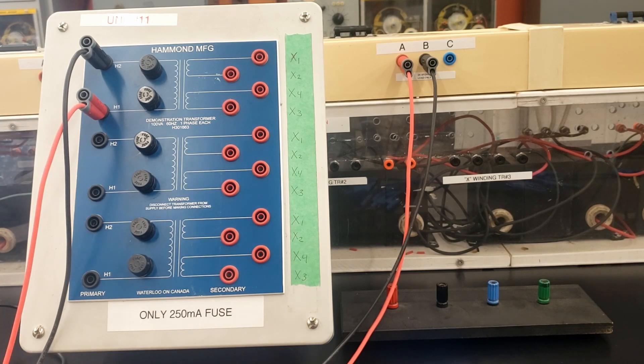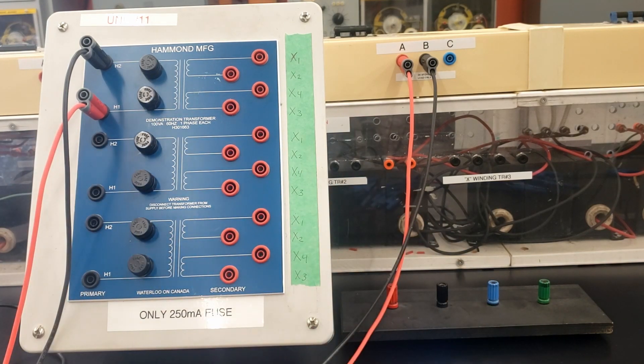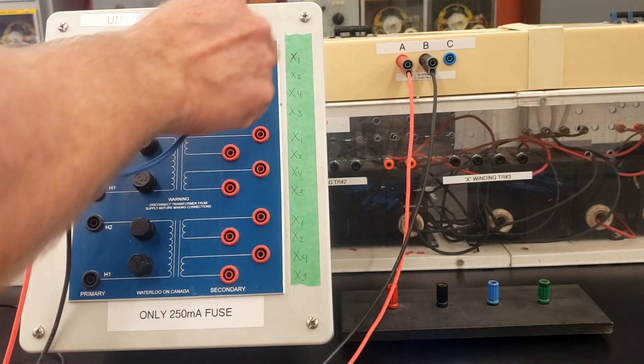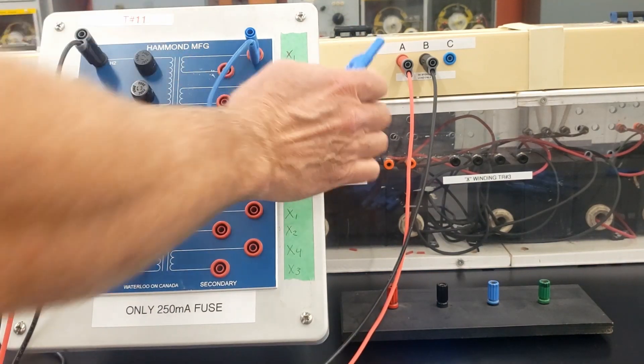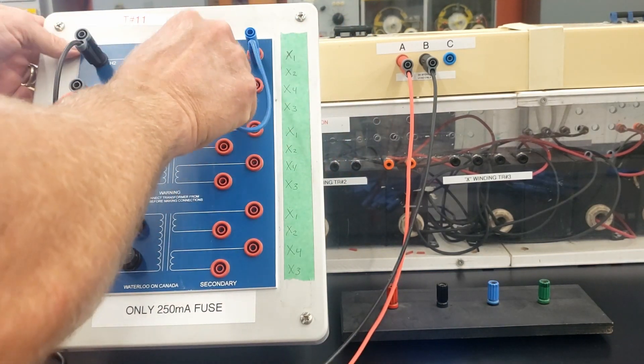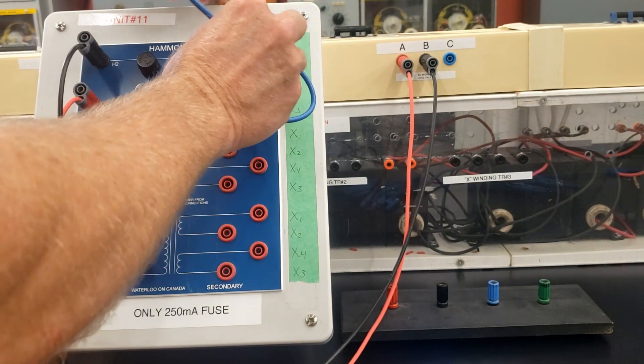We're doing the lower voltage connection. So, I'm going to parallel my secondary. That means that I'm going to connect up X1 and X3. And I'm also going to parallel X2 and X4.